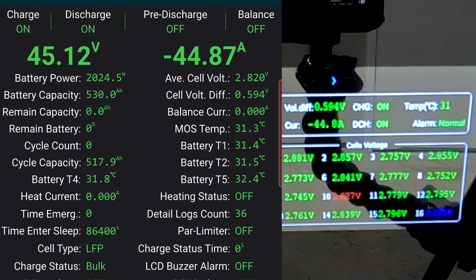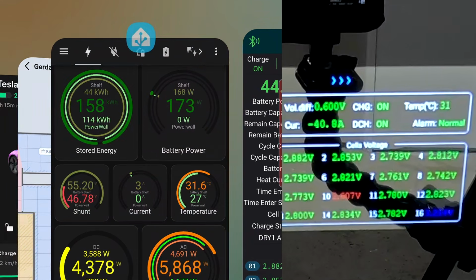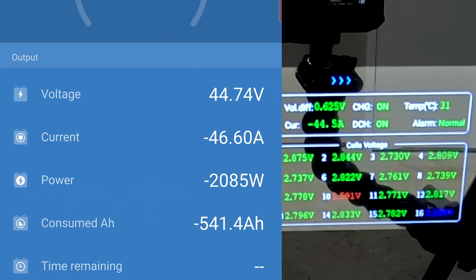So we had 45.1 volts pack voltage, discharging with 44 amps. The remaining battery has just changed to 0% here in the BMS because we have reached 2.7 volts - this is how it is set. The cycle capacity is only 518.2 ampere hours, and that is in contrast to the smart shunt, which says we have discharged 541.5 ampere hours. Now we have 46 amps in the smart shunt, and over there only 44 amps, so that's why the BMS is a bit lower.